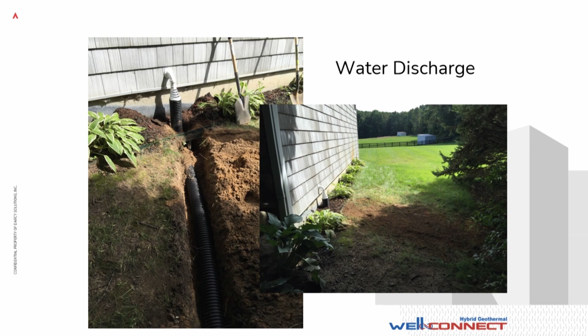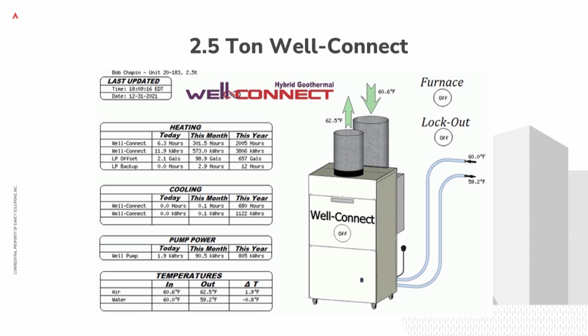The water is then discharged out to the ground, much like you'd see a sump pump discharge. And again, with these low flow rates, getting rid of the water is really quite easy. Every one of our systems has a real-time monitor on it, so I could show you on your phone your system running. I would just direct you to the hours. This is a full year, so the system ran 2,000 hours. The furnace ran 12 hours. That's an entire winter. We also show the well pump kilowatt hours that are used to get that water to the surface, and we also show the cooling capacity. So out of all of our systems, on average, we are doing 90% of the heating and all of the cooling.